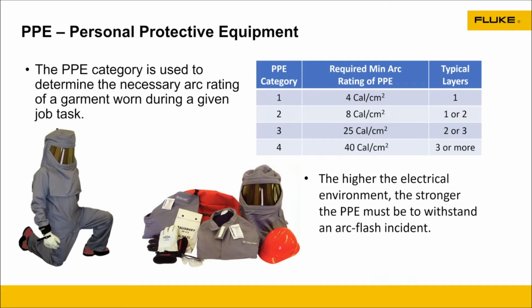Part of that standard is PPE. PPE is crucial. Now, PPE could be your safety glasses, maybe a hard hat, obviously steel-toed boots, depending on the environment, or gloves, hearing protection. But when we start working with electricity and the potential energies around there, that's where our category rating can actually increase, and having the correct gear on. Cat 1, I can see this at times, it's cotton jeans, burn-resistant material on your shirt.